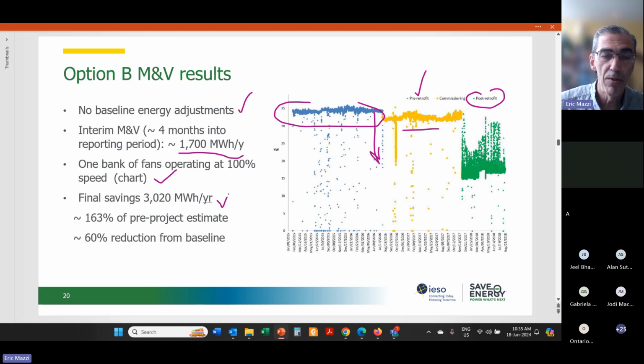After some forensic investigation and some reprogramming, we allowed all of the fans to run through at least 12 months of post-retrofit. Then the final savings came out to over 3,000 megawatt hours per year. That was about 63% higher than the pre-project estimate, and it represented roughly a 60% reduction from baseline.